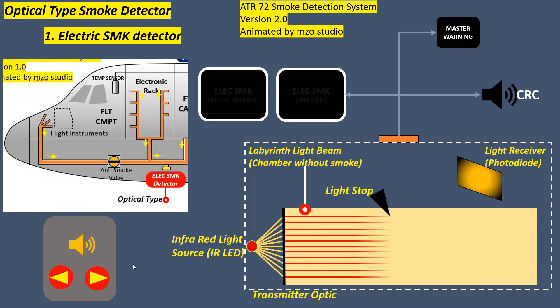The light source IR LED, the light trap, and the light receiver photo diode are arranged in such a way that the light from the emitter cannot reach directly the receiver. Brief light pulses are transmitted periodically by the IR LED into the measurement chamber.